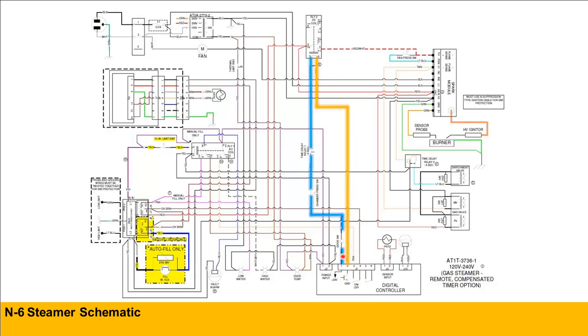So as DC voltage leaves, first stop is going to be the door switch. Sorry, let's back up a little bit. Let's make sure that we actually have a DC output from the control board. At this point, I'll ask you to remove the black or red wire. That wire color has been changed, but it's a thin wire right next to the orange. I'll have you remove both wires, and you'll actually have to test across two pins. So pull the wires off. Do we have 24 volts DC output from the control board? No output. If we have no output, then we definitely have a defective control board.